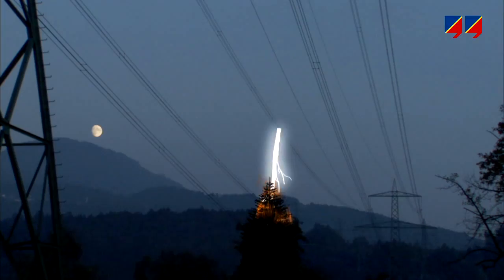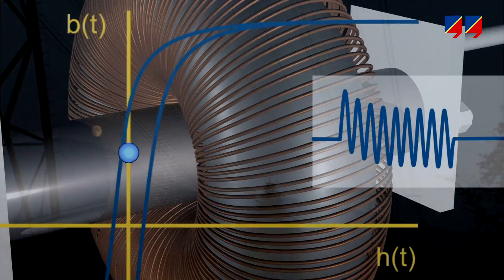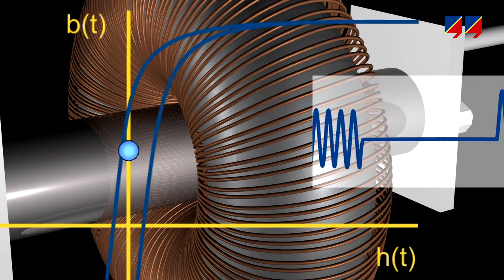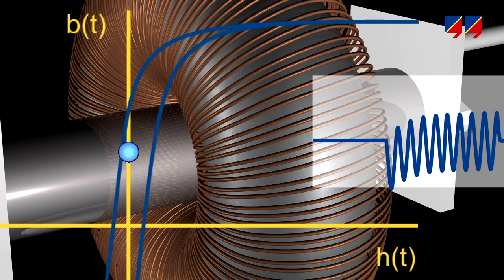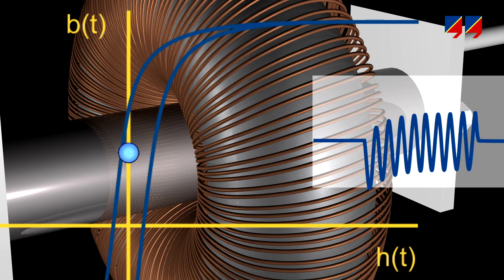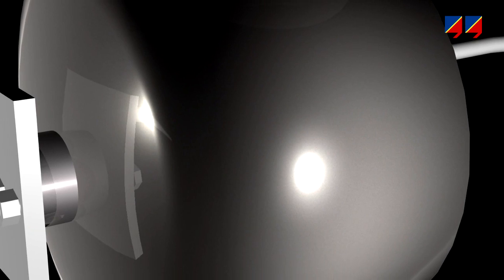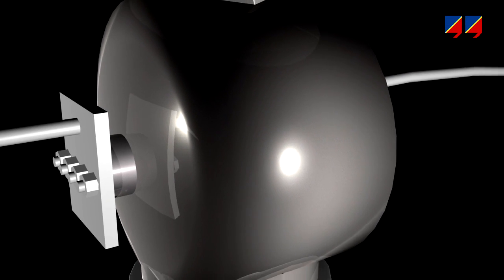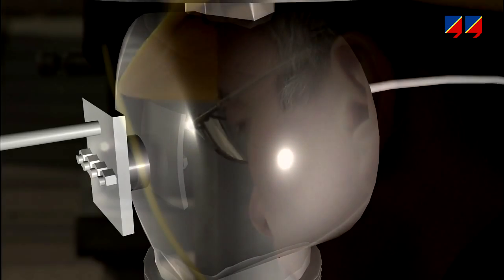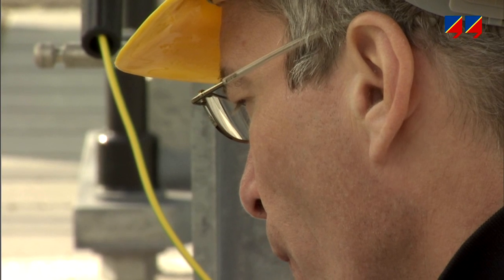During the lifetime of a CT, many faults have to be cleared. Each of these faults may add remanence flux in the core, in a positive or negative direction. For normal operating currents, the CT's performance may be as usual, so the operator does not have any indication of this effect.